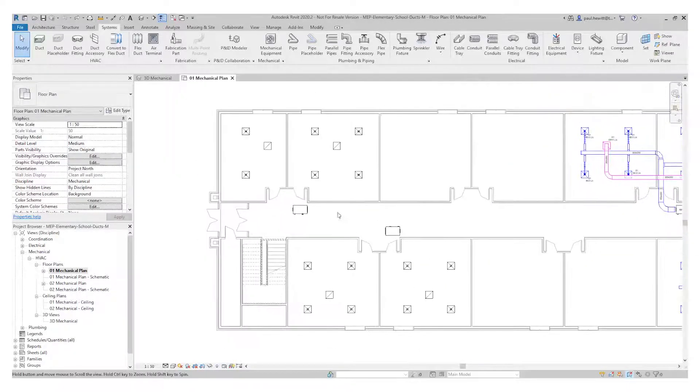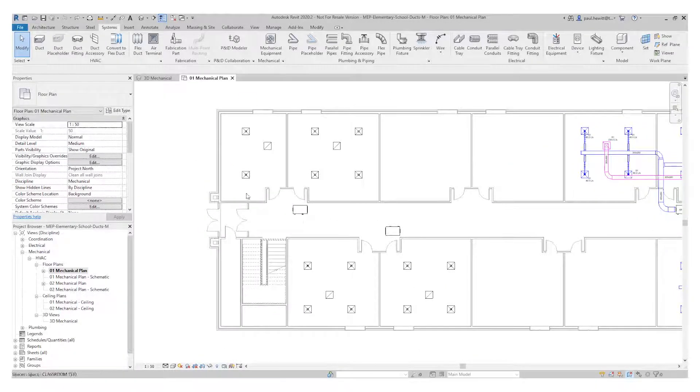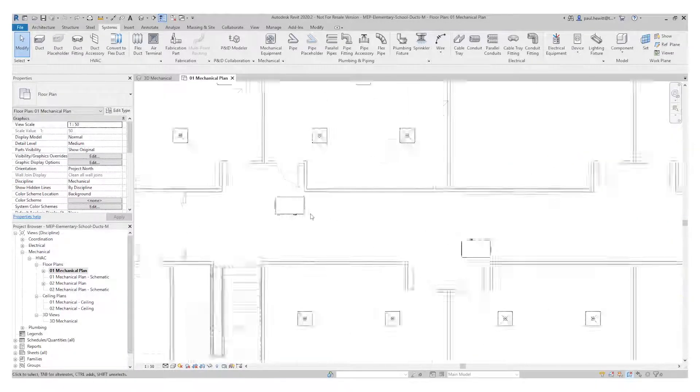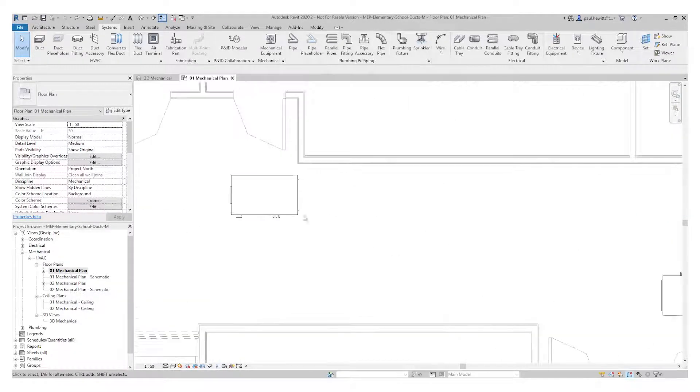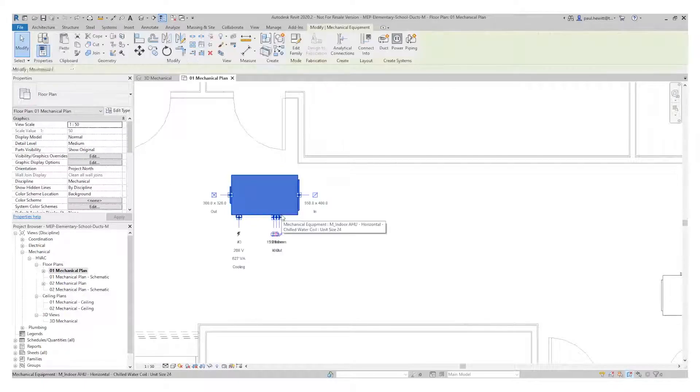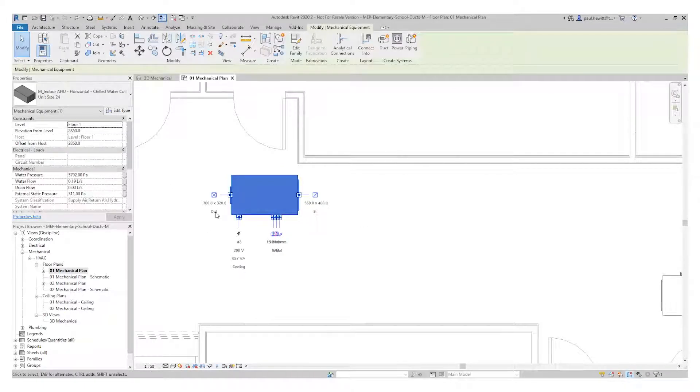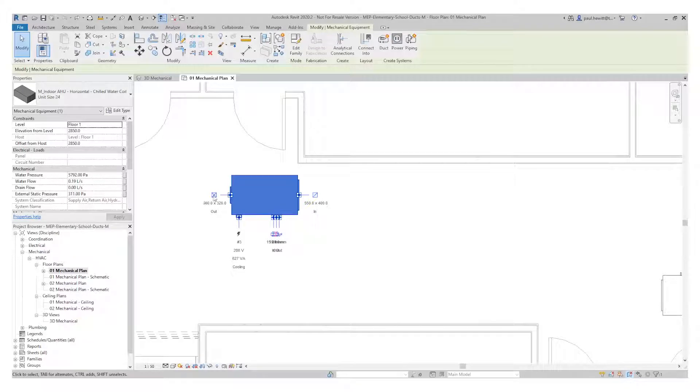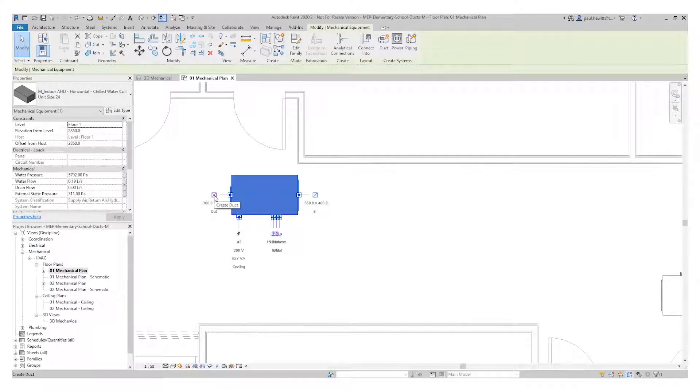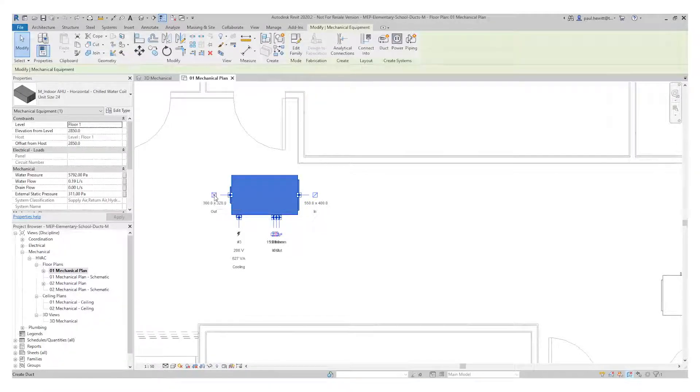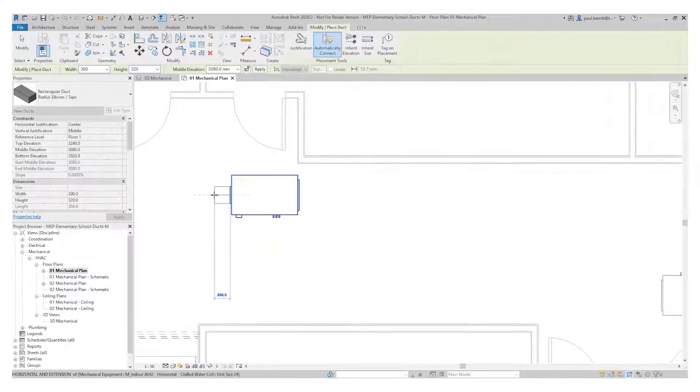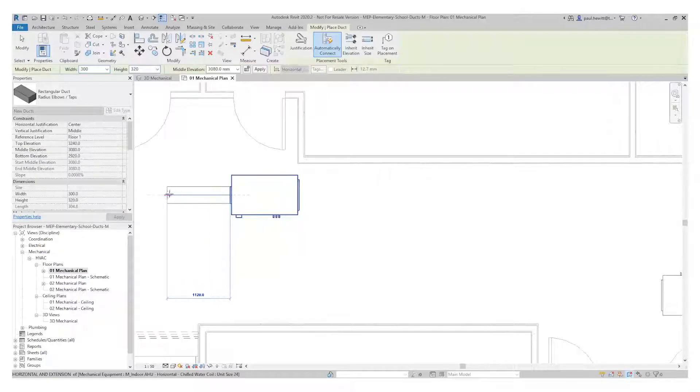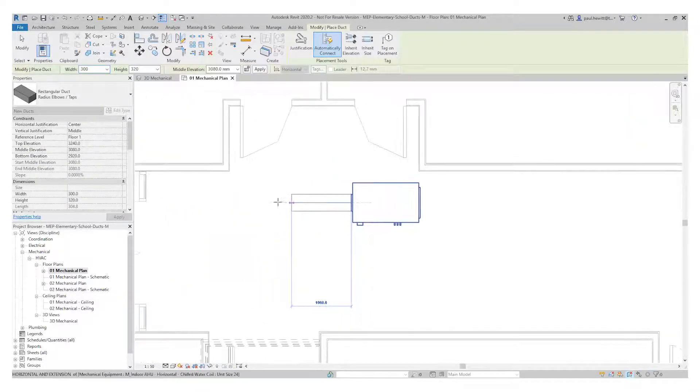First thing I need to do is open the mechanical plan and zoom into the air handling unit. When I select this you'll see we have the connectors that are available to us. So in this case what I need to do is select the connector for the out and it will automatically give me the ductwork at the correct size.